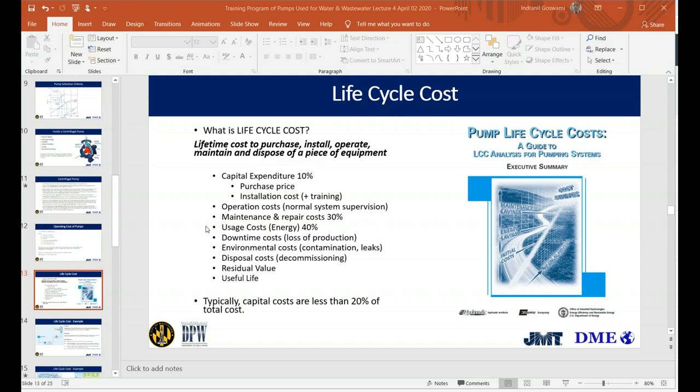for example, let's say that your analysis leads to a pump house with four pumps where the fourth is redundant to handle the capacity, you need three, which means you are increasing your costs by 33% to handle the downtime, because you're adding one to the array to have the option to have three pumps service the peak flows and have one taken down at the same time.